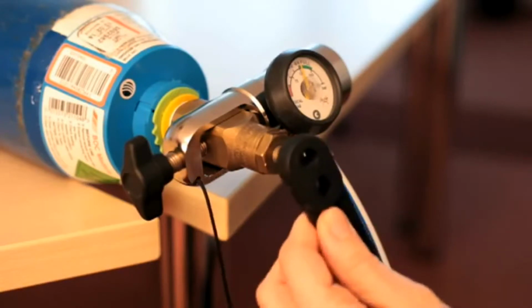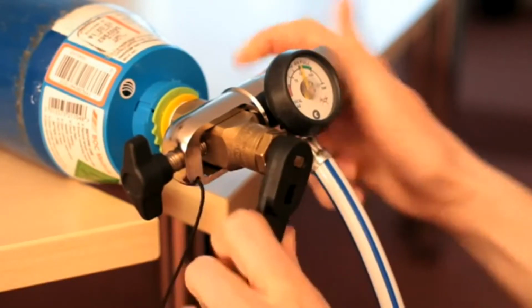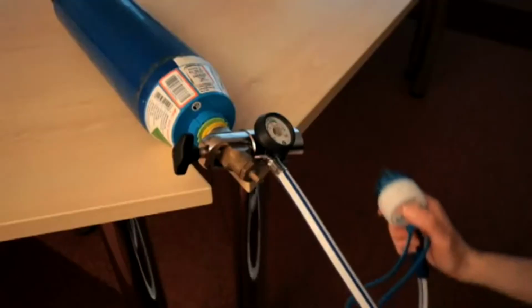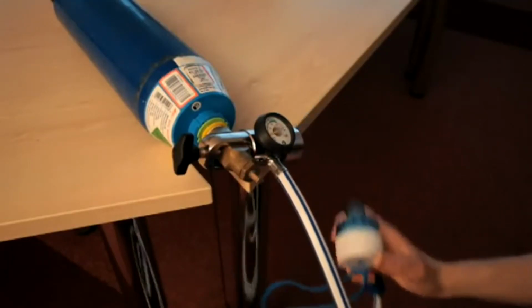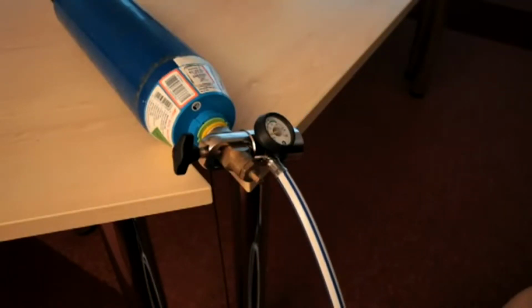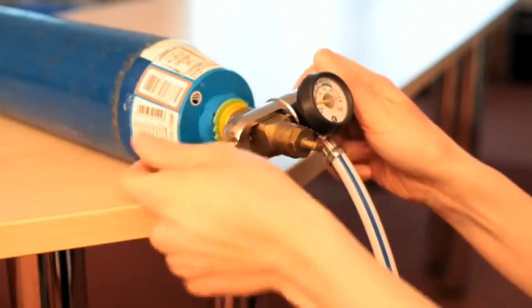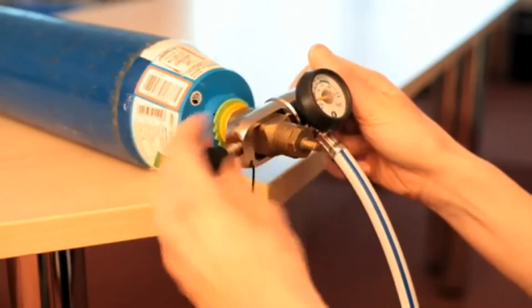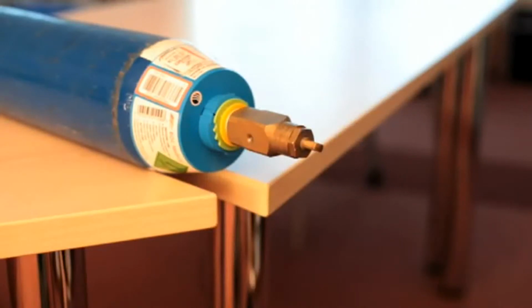To change the cylinder, turn the gas supply off and depressurize the system by depressing the demand valve test button. Release the regulator T-bar until there is sufficient clearance between the yoke and the valve. Remove the regulator from the cylinder.